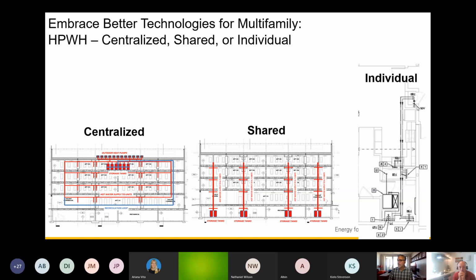That means for the developer, hear me: you only need a cold water line to each unit. That's all you need - it shows up and you're done, no need to plumb hot and cold. The centralized system needs dual plumbing throughout the building plus a recirculation line, so the complexity of the plumbing is really high. The shared configuration is less complex, and the individual unit setup is the simplest and cheapest in plumbing dollars.